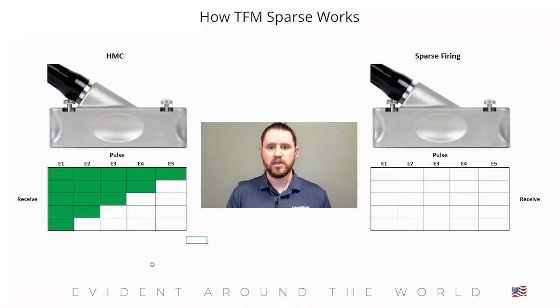But in an instrument like the X3, where we are summating all of the data through the hardware of the unit, a better way to improve upon the inspection speeds is, instead of reducing the amount of received elements, to actually reduce the amount of pulse elements. So in the sparse firing technique, we can program the instrument to reduce that number and fire, say, every other element or every other 2 elements or at certain intervals to speed up the process. So in the sparse mode on our right-hand side, we might reduce that by a factor of 2.